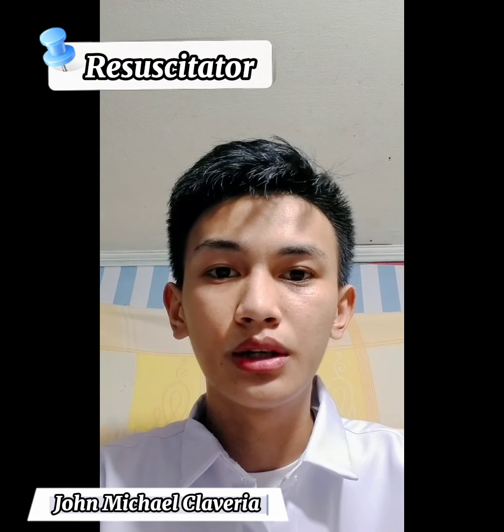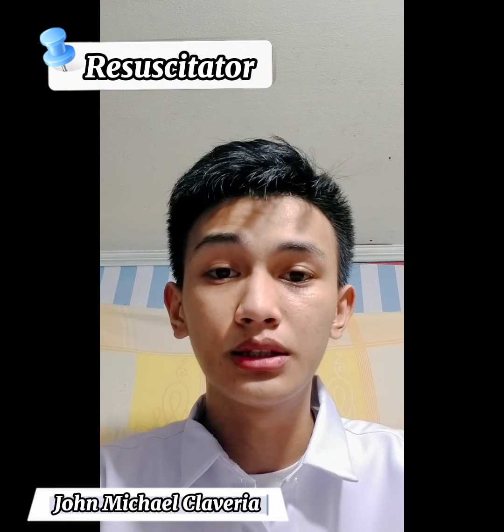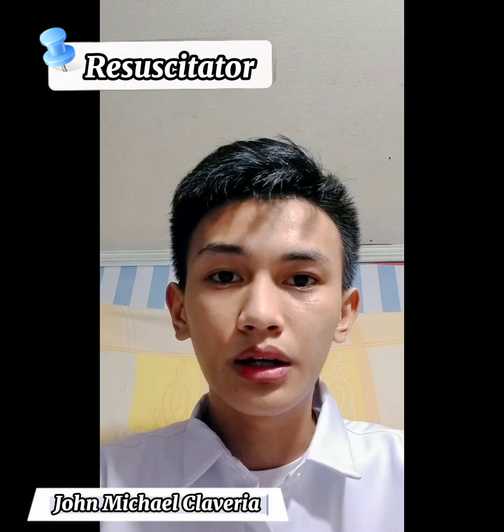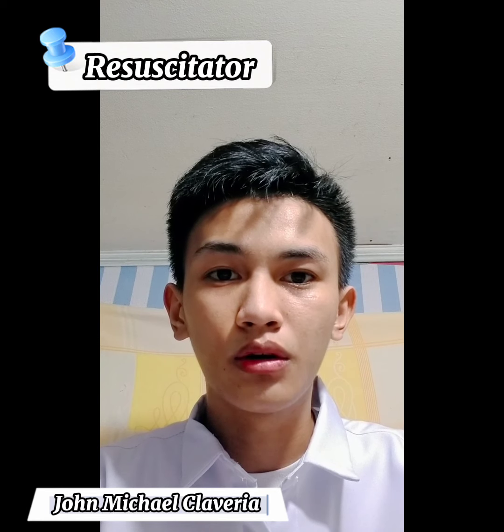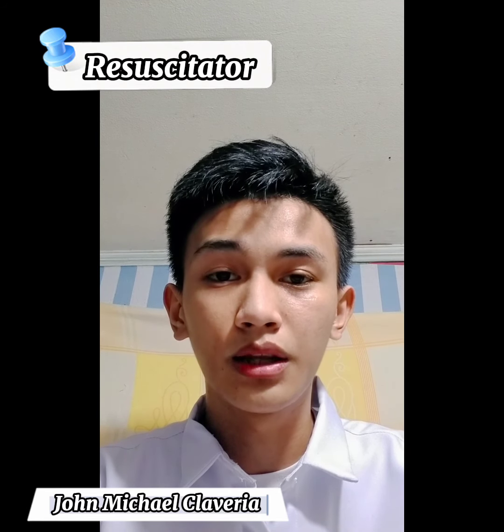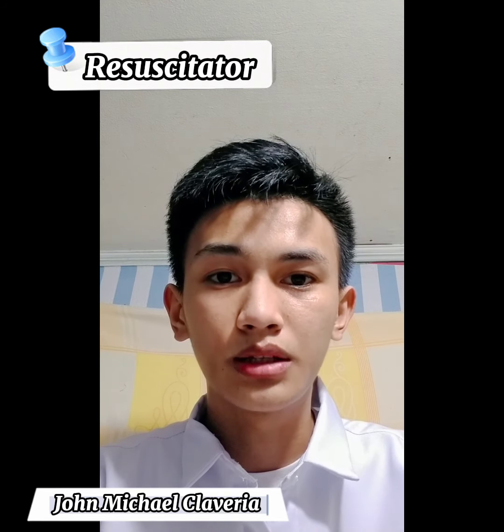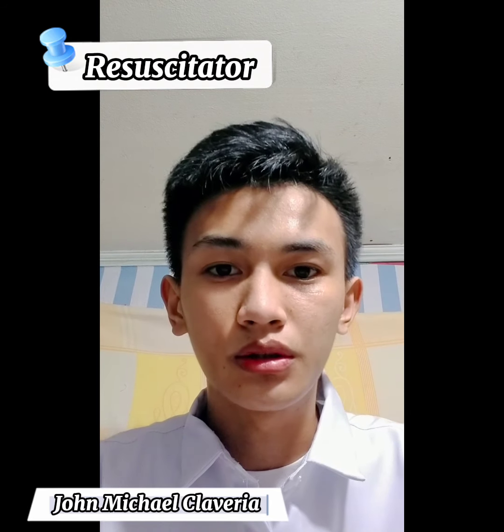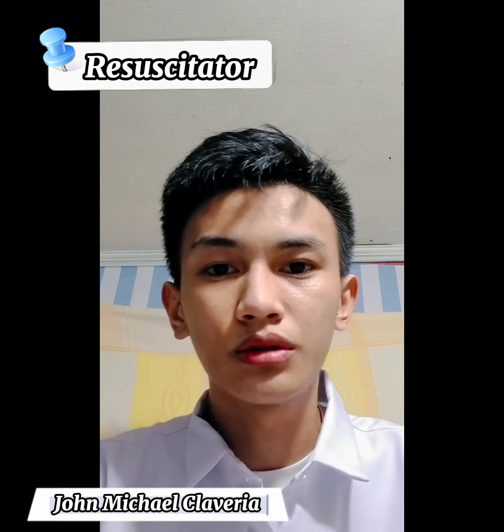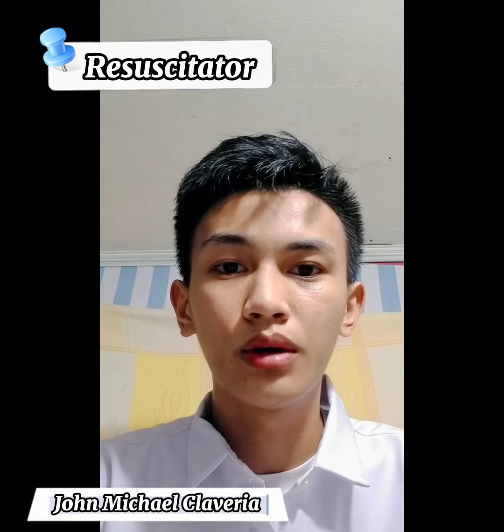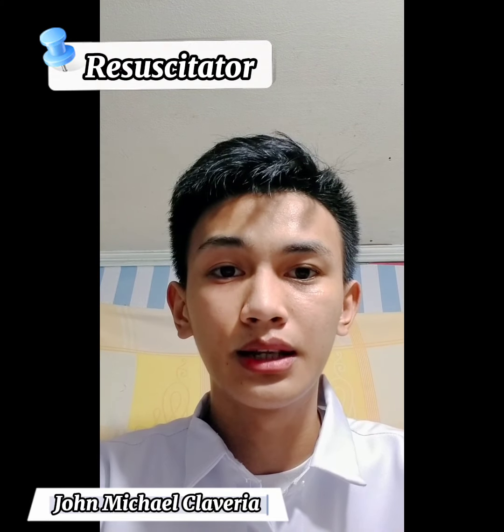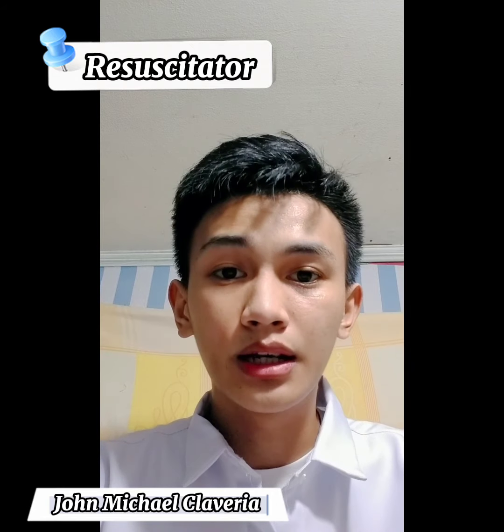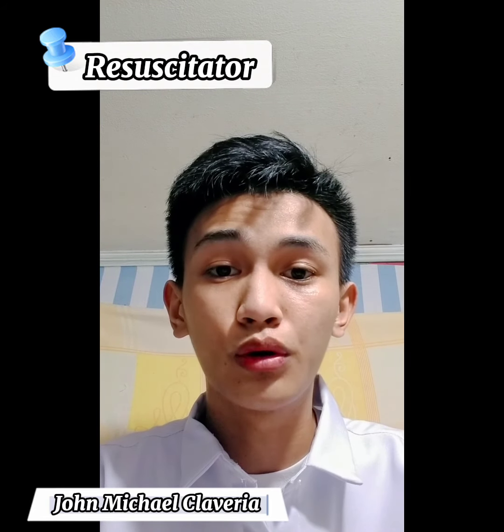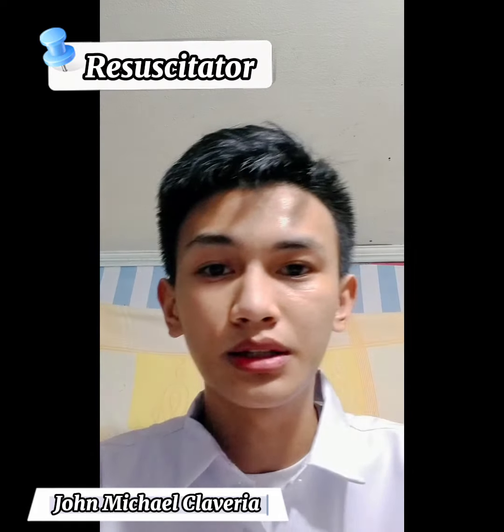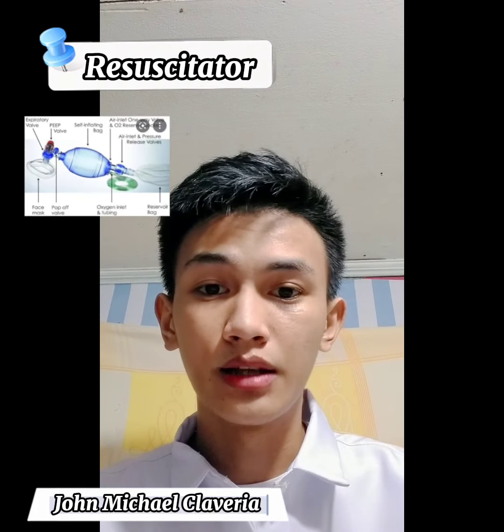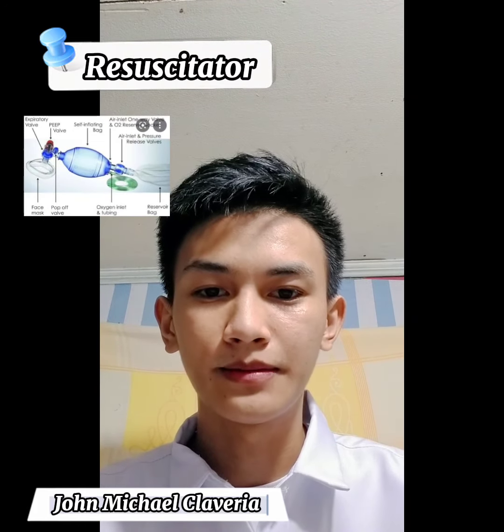Gas-powered resuscitators are driven by pressurized gas delivered by a regulator. The resuscitators are powered from a 50 psi oxygen source and connected to a standard 15 and 22 millimeter circuit fitting for face mask tubes. Gas-powered resuscitators are superior to manual resuscitators because they can deliver 100% oxygen and they require little effort to ventilate the patient. Gas-powered resuscitators are recommended for use on adults and not for infants and small children. This is an example of resuscitator equipment.